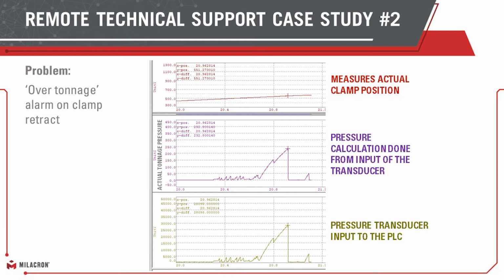So we were very quickly able to connect to the control, see that this issue was actually occurring, and then from there we dug down and started plotting and looking at what is the clamp doing, where is it while it's operating, what is the transducer output saying, and how is our drive and how is our system calculating what that actual tonnage is, so that we can try to eliminate any other occurrences outside of the issue actually happening.